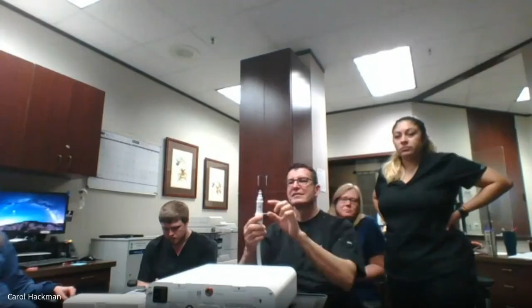It'll snap in. And you turn the system on first. So don't pop one on yet. The mode of operation is you turn the system on when you're ready to do the treatment. So you've communicated everything to the patient, you're ready to go, the patient's ready. Then you turn the system on, and the last thing you do is pop your tip on, just to give yourself the max possible treatment time if you want to use it.